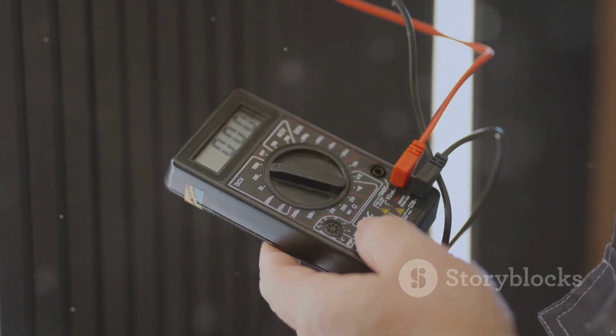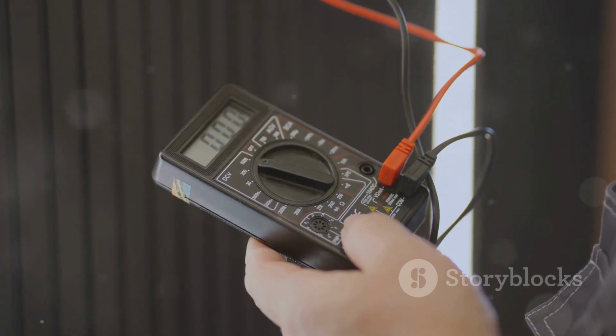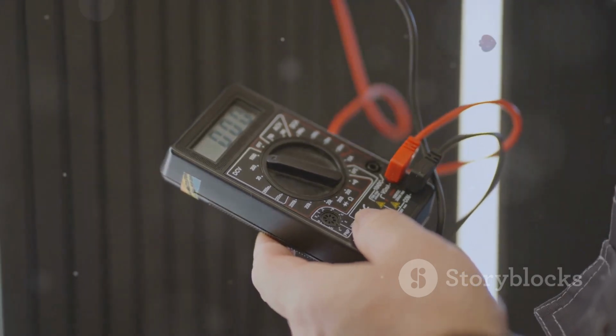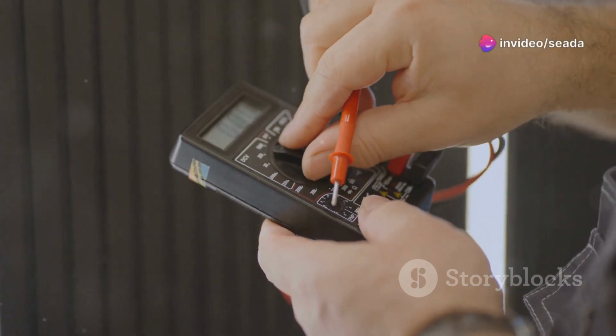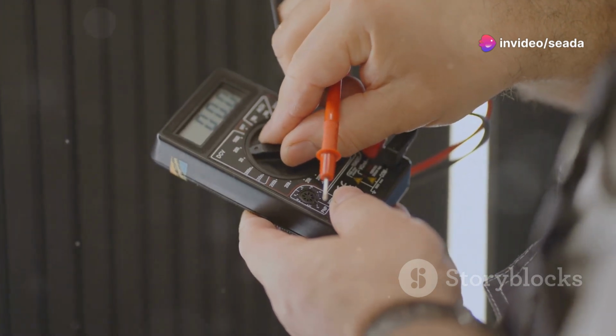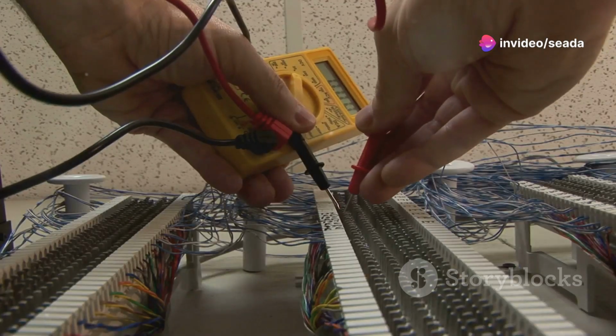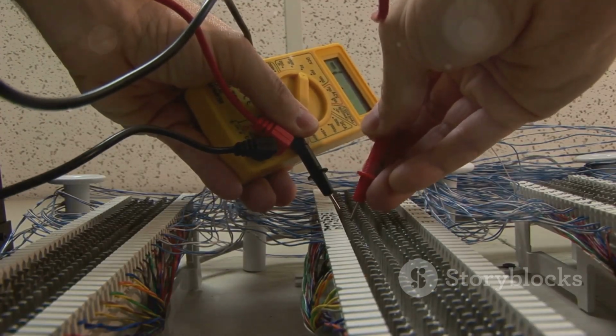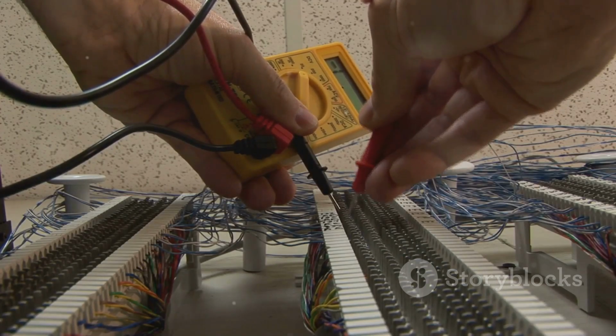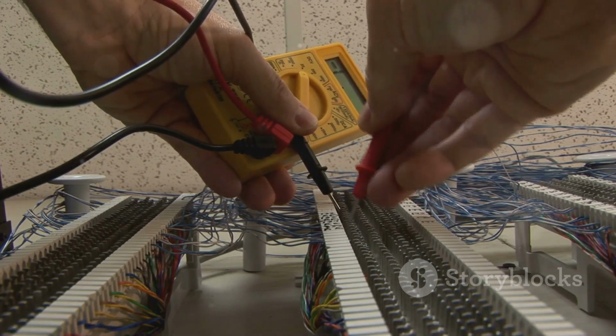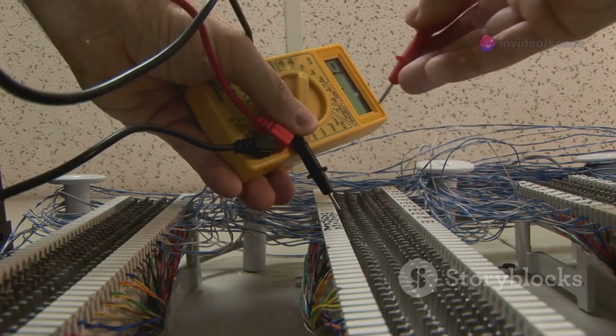Never assume a circuit is safe just because the breaker is off. Set your multimeter to AC voltage and check the main isolator. You should see 230 to 240 V. This confirms the supply is present and your meter is working. Test the tripped MCB's outgoing terminal against the neutral bar. It should read 0 volts. If you see any voltage here, double-check your isolation.